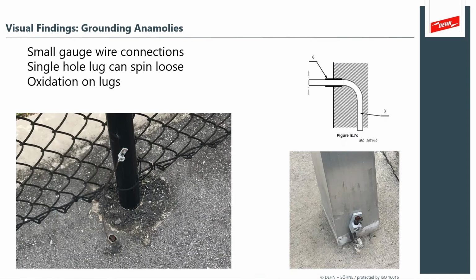Visual findings. You often see pigtails emerge directly out of the concrete, and there actually are IEC standards that describe specifically that conductors should have a covering. Like you often see a vinyl coated conductor emerge through the concrete. This is a little bit substandard here. You've got oxidation on the lugs. You've got a single hole ground lug that can spin loose. So it's good to understand that grounding anomalies can be a direct result of the installation. So it's really important to understand what you're looking at.